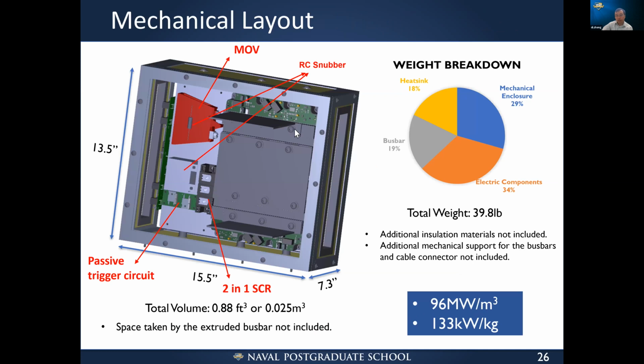Mechanical layout. So this is two devices. We have two IGBTs per pole, in series. And this is just a regular bus bar, there's no lamination at all, with the gate drive. This is the MOVs, and this is the thyristors, where we take the 2-in-1 SCR, because SCR is very good at handling surge current, and it's very compact. And this is just a passive trigger circuit. This is already for two thyristors. In this design right now, we're still using some regular RC snubbers to try to slow down the dV/dt. It makes everything softer. We're already cutting a high current, so we want everything as soft as possible.